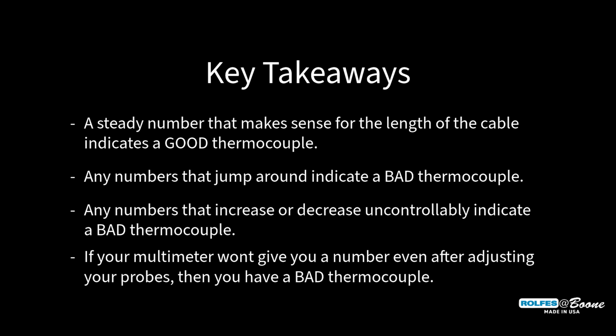Let's review some key takeaways. A steady number that makes sense for the length of the cable indicates a good thermocouple. Any numbers that jump around indicate a bad thermocouple. Any numbers that increase or decrease uncontrollably indicate a bad thermocouple. If your multimeter won't give you a reading, make sure you are on the resistance mode. This setting is indicated by the omega symbol in the Greek alphabet. If you still aren't getting a number, make sure your probes are touching the metal on the inside of the crimps. If you still don't get a reading, then you have a bad thermocouple.